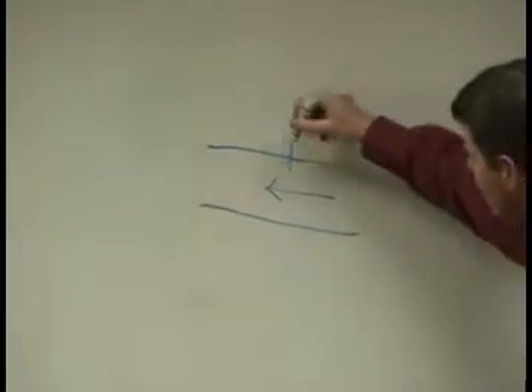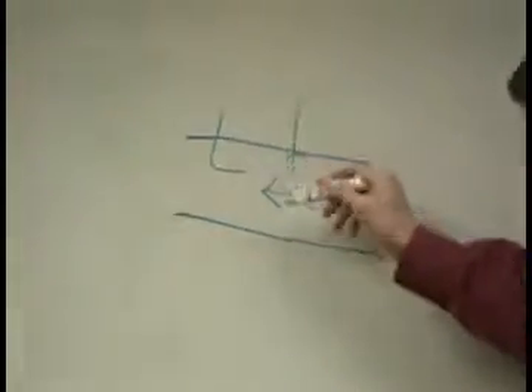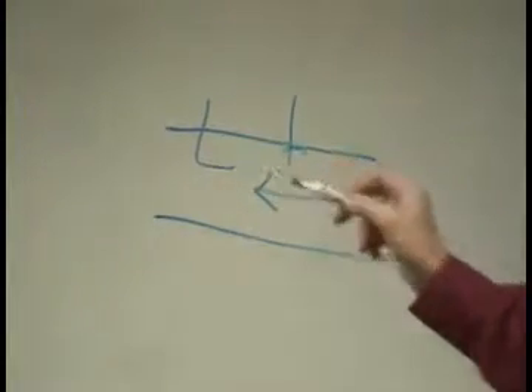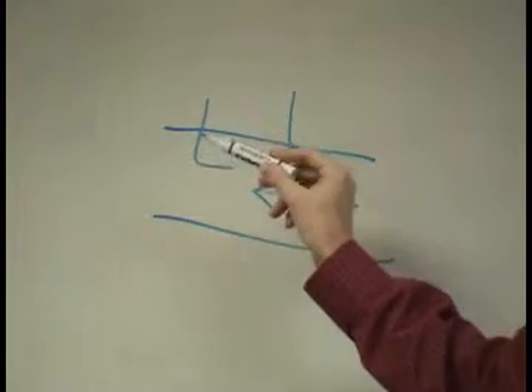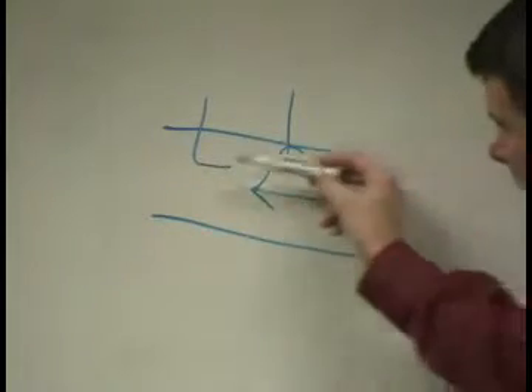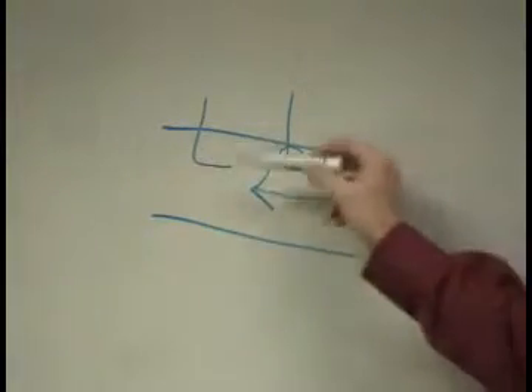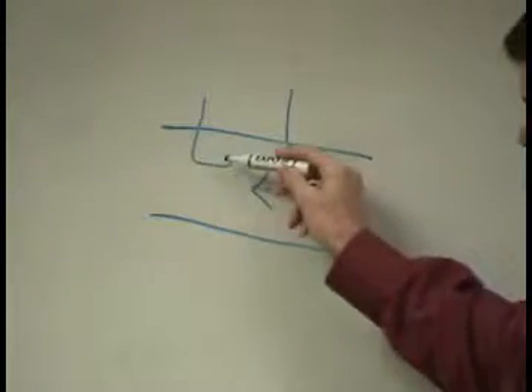And that's usually what will control that, like the VFD, to maintain duct pressure, that duct static pressure. This pitot tube, the opening is pointed into the flow, so the pressure going in here is the total pressure. That is going to be the pressure of the air being forced into it because it's blowing right in, and the static pressure. The difference is called velocity pressure. When you subtract the static pressure from this pressure coming in, you get velocity pressure.